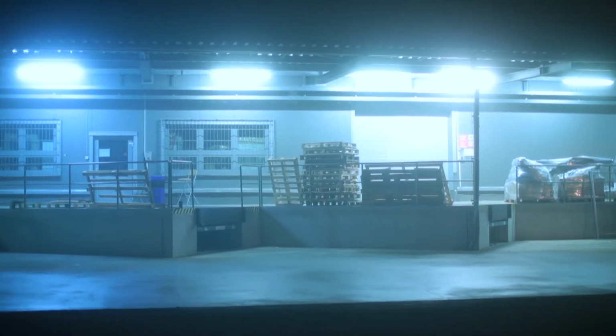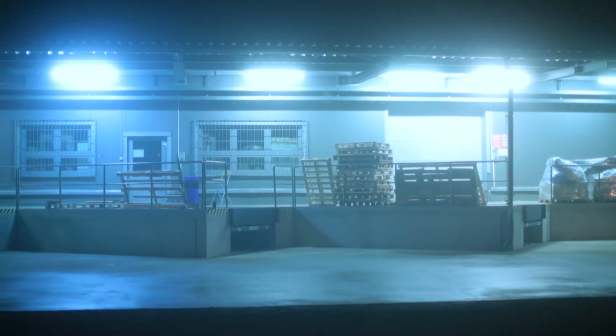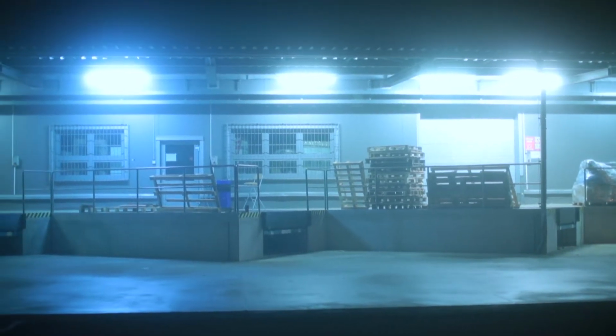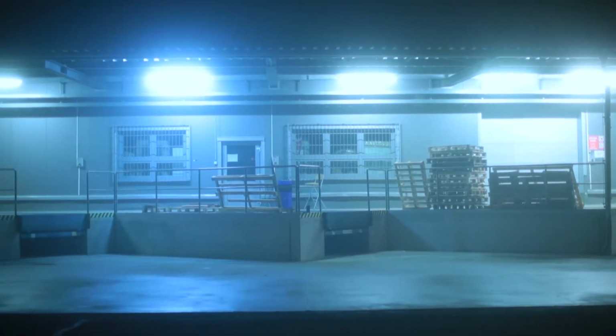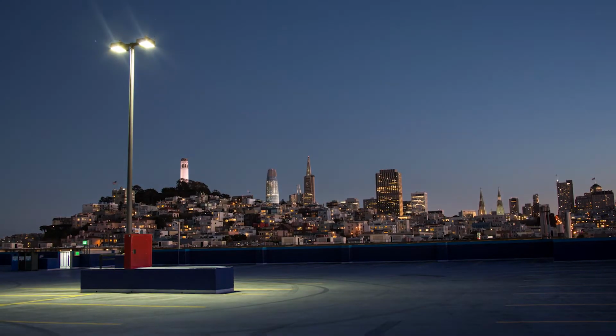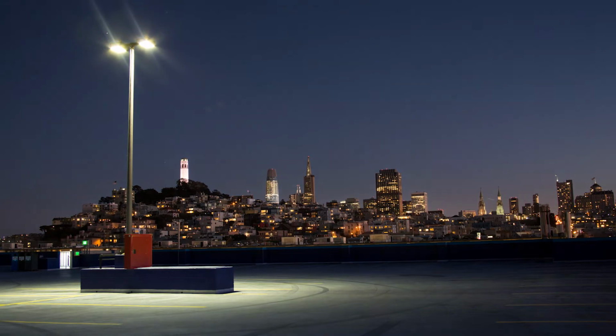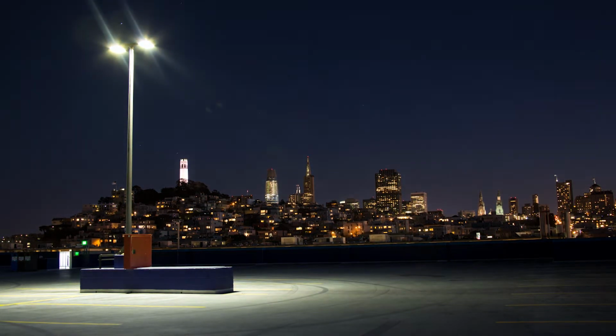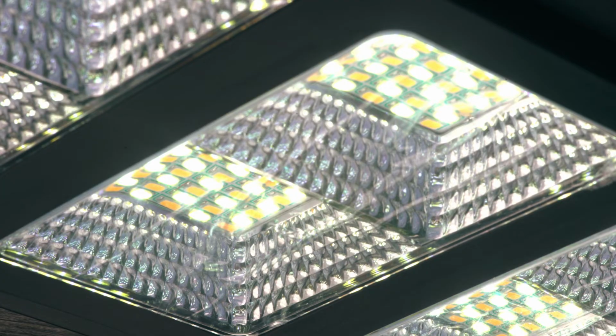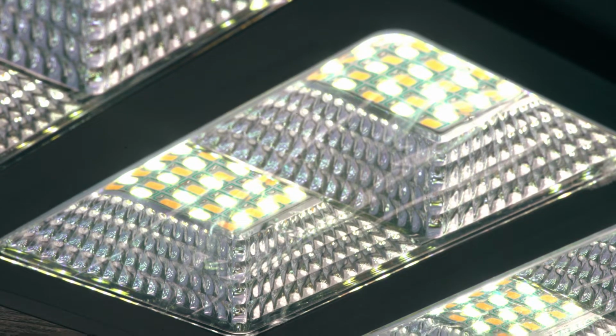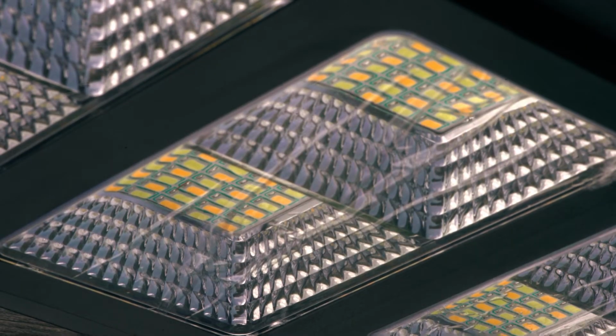A common strategy is to operate lower wattage building-mounted fixtures from dusk to dawn to meet egress and general safety and security needs, while a significant portion of the area or pole-mounted lighting dims or turns off at midnight or within an hour of building closing. This is a simple multi-zone time clock solution.